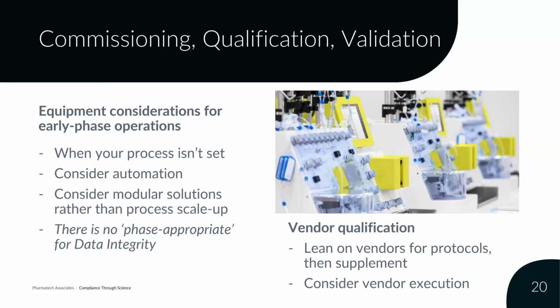That's not a bad thing to do. It just makes writing the URS really difficult because you can't put process parameters in there. So to ease that challenge, and this is something risk-wise, you have to buy into this with your whole chest. You say to yourself, if my user's requirement is that they want this machine, then we have to trust the machine to be doing the things the user requires it to do. And then we simply prove to ourselves that the machine is doing what it purports to do. It's a little convoluted. I'm going to say that one more time.